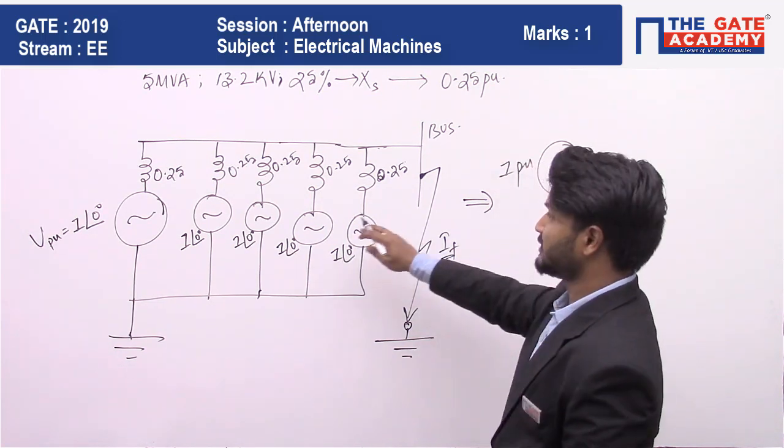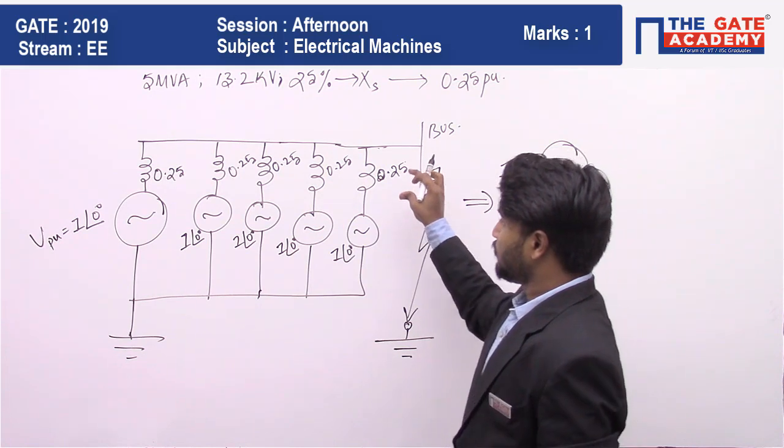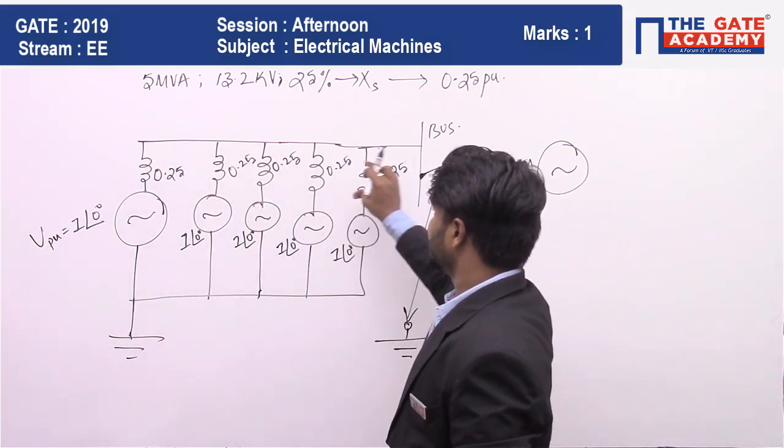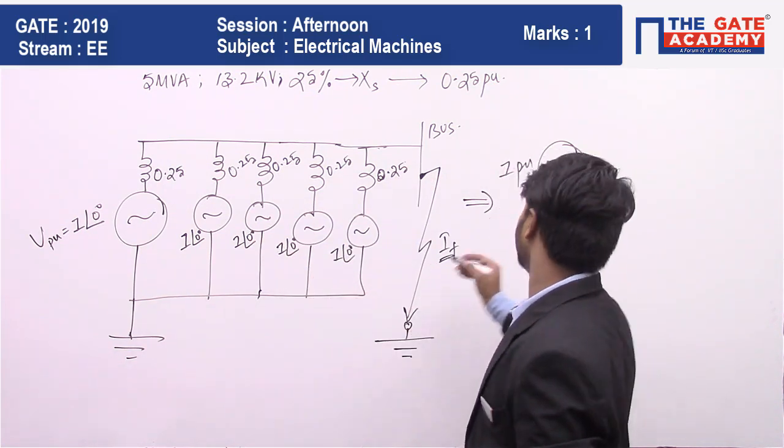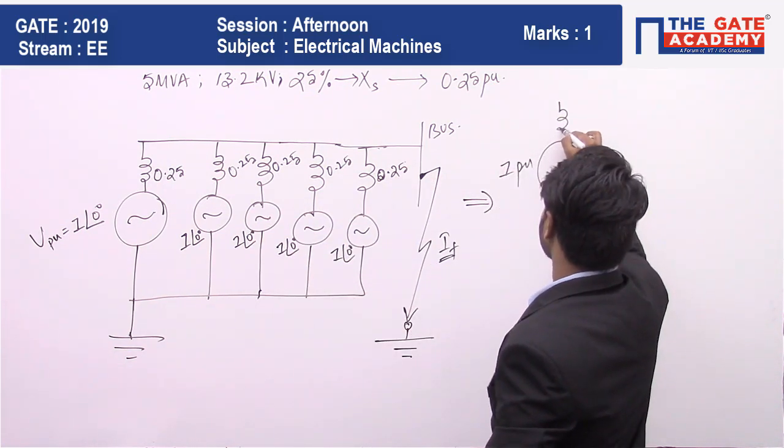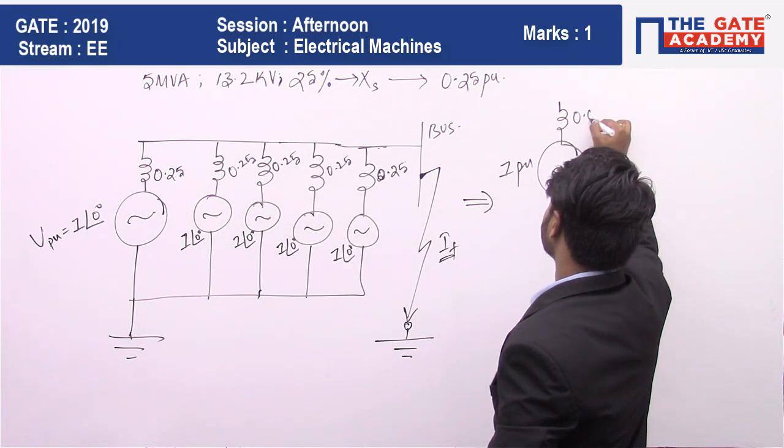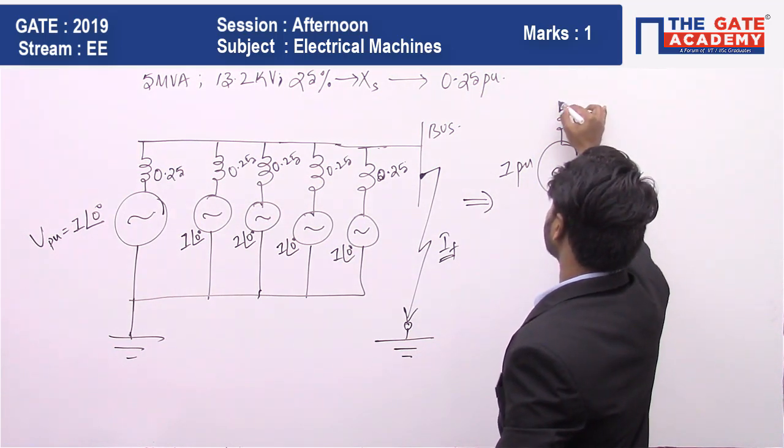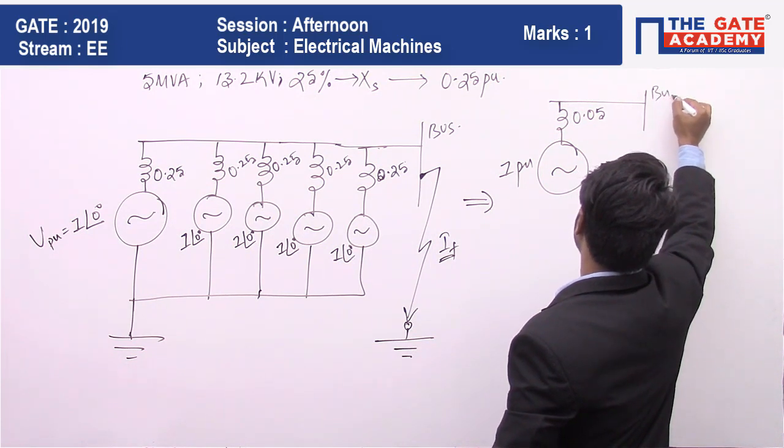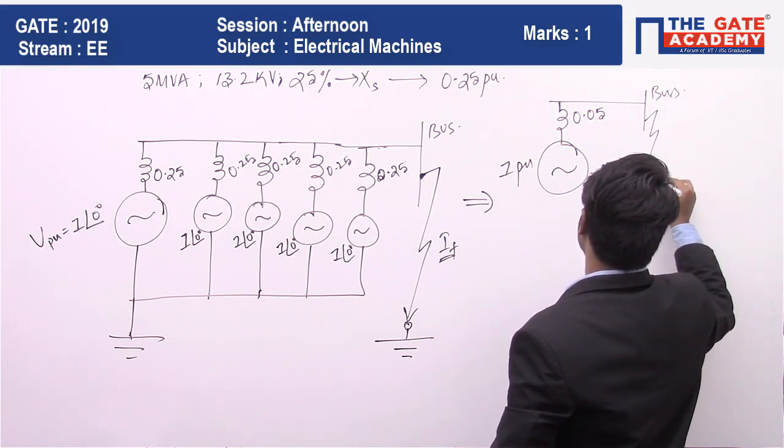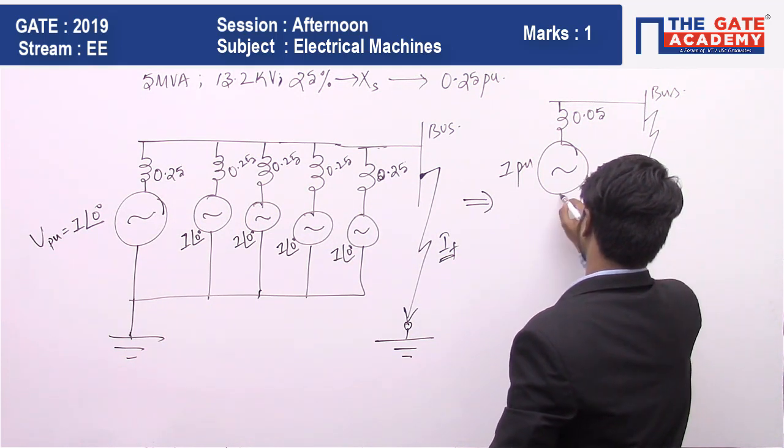Single voltage source with 1 per unit as its voltage, and five reactances in parallel—0.25 divided by 5, you will get 0.05. Five reactances in parallel connected to the bus, and fault level in MVA we need to find out.